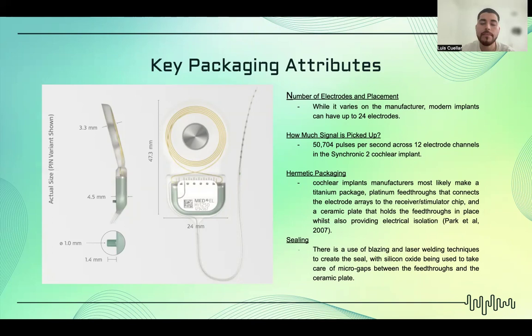Other key packaging attributes to talk about is definitely the hermetic packaging, right? So as far as the internal unit is concerned, that's obviously interacting with a lot of the bodily fluids that we have inside, right? So how does that prevent the entering of moisture? According to a study done by Park and his colleagues in 2007, they were designing a simple cochlear implant design, and they used a lot of the materials that we actually discussed in class. They had a titanium package, they had platinum feed-throughs that connected the electrode arrays to the receiver chip. And they had a ceramic plate to hold the feed-throughs in place, right? So this is very in line with what we've talked about in class.